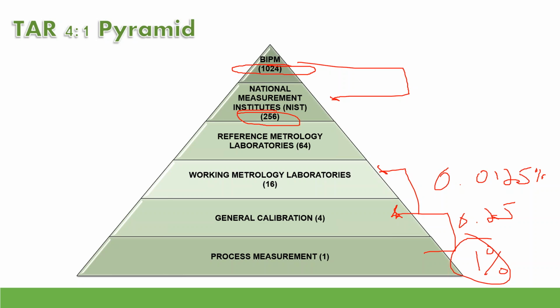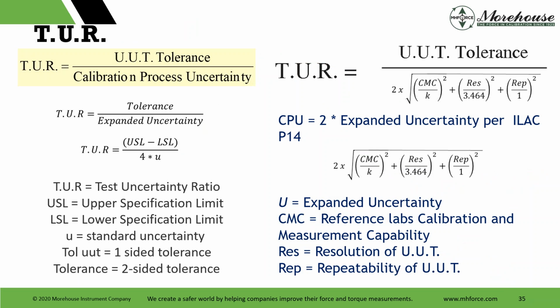we have all these instruments and all our references are 4 times better, they're going to calibrate all the field instruments, and we're going to insist on that, and we're going to use primary standard laboratories to do all our calibrations, that is most likely maintainable. Though when you start trying to propagate this up, it's just not. You're not going to be 4 times better, and then 4 times better again, and then 4 times better. It's just not going to happen. Not maintainable.